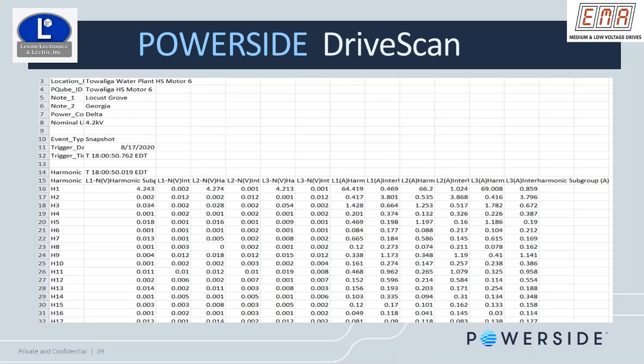Real life time - one of the things I mentioned and have on this slide as well - this is all happening at 30 microseconds, so very quickly. It's very fast. What we call ultra harmonics - these days we have so many switching devices that our grid and our facilities are bombarded with harmonics. So we can now see ultra harmonics with this device. It's very useful in terms of how quickly it can read this data.